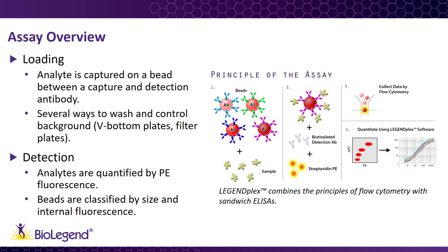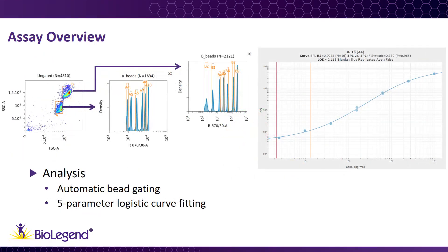Users have the option of collecting directly from the 96-well plate or from FACS tubes. Data analysis is performed using our free, cloud-based software. As seen in the figures on the left, the software automatically finds and gates the beads based on forward and side-scatter profile, followed by internal APC fluorescence. As seen on the right, it uses a five-parameter curve-fitting algorithm to generate a standard curve for each analyte from the provided titrations. Samples are then quantified based on these curves.